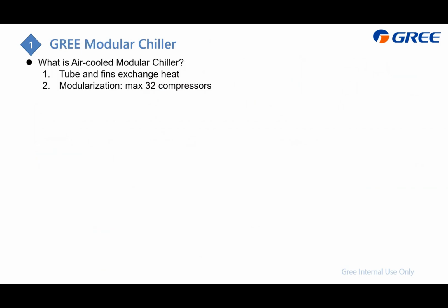Maybe you have a question: what is an air-cooled modular chiller? Just like its name, air-cooled means in cooling we need to release heat to the air, and in heating we need to absorb heat from the air, with the tube and fins heat exchanger. Modular means we can combine different outdoor units or different heat pumps together to enlarge the capacity. The maximum is that we can modularize 32 compressors together.